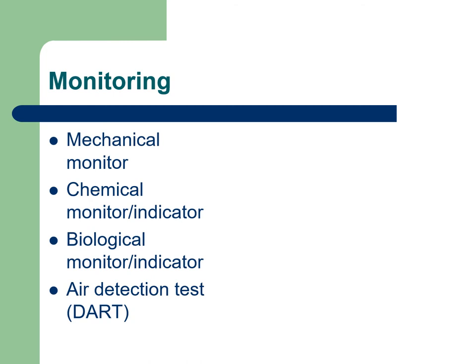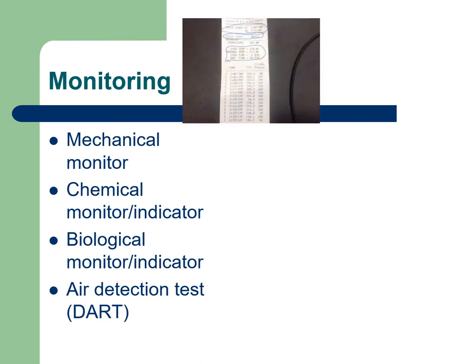First and foremost, I want to talk about the mechanical monitor. Here on your screen you should see a printout, it looks like a receipt, and this is what the steam sterilizer will print out. You can see some things circled, but it's kind of hard to make out the numbers. When we get something out of the steam sterilizer, or any sterilizer for that matter, we want to check the mechanical printout. This tells us whether it reached the temperature it was supposed to reach. We wanted to sterilize it at 270 degrees for 4 minutes, and we want to look and see if it met those parameters. So that's our first method of checking.